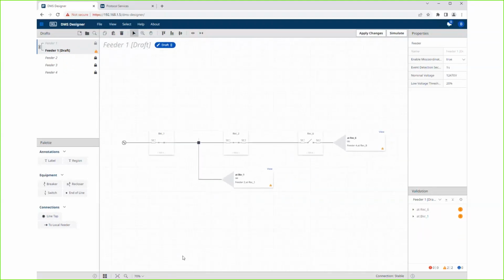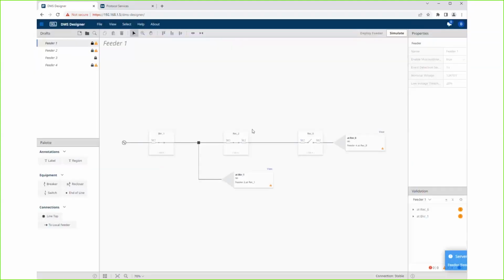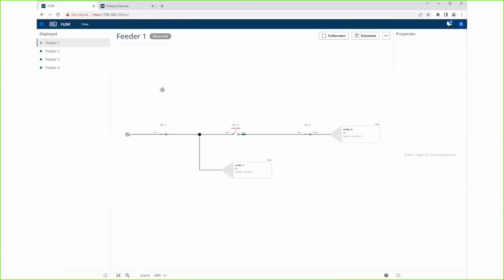Recloser 4 is no longer there. Now, FLISR is still running, and it's running with Recloser 4 until I apply these changes. So I'm going to go ahead and apply these changes, which overwrites feeder 1. And now I'm going to go back to FLISR, and let's see what we've got. So we now have feeder 1 with no Recloser 4 disarmed. So I can come in here, arm it, throw the exact same fault at it again, and it'll work. It will not try to operate Recloser 4 because Recloser 4 is no longer part of the FLISR settings.